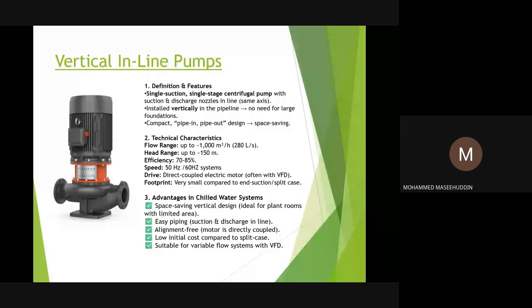Now there are pumps which have come with a built-in VFD, where the VFD is mounted on top of the motor itself, so that you don't need a different control panel where you have all these VFDs, and then give the power supply from there to the pump, and the pumps are running. The pumps which are coming with built-in VFD are more prominent now, and are being used in most of the projects.